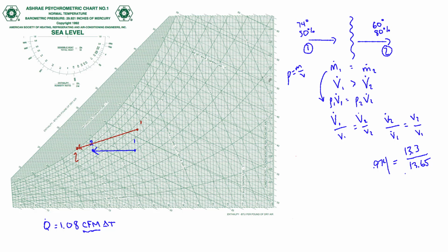So now, what does that change for our coil situation? Let's draw the coil again. We have our 74 degrees and 50% humidity and M.1 entering the coil. But now we're going to do some latent cooling, which means that condensate is going to be removed from the air. Water vapor is going to be removed. So let's draw a little drip pan underneath the coil here. We have M.condensate leaving the airstream, and then M.2, which ultimately leaves the coil, is at 55 degrees and 100% humidity. Ultimately, we'll probably do some bypass and some mixing, but I don't want to complicate things.